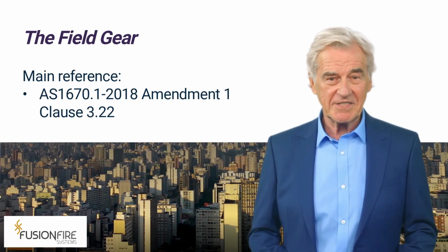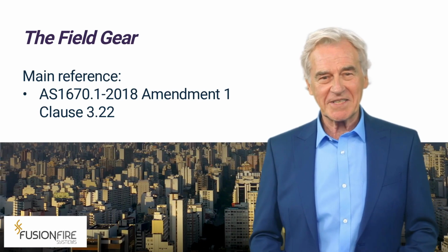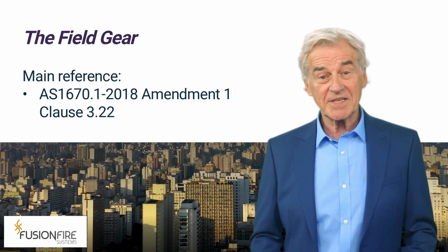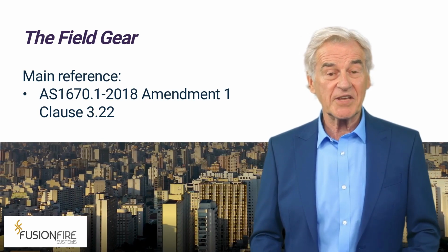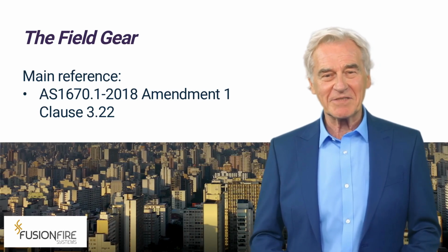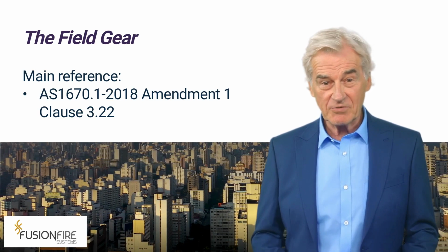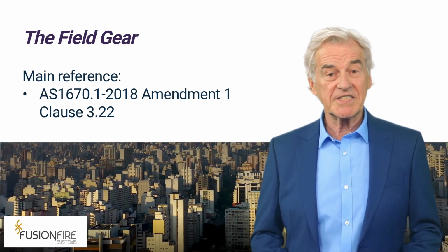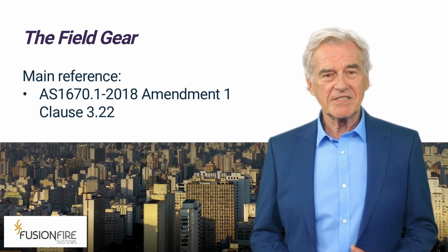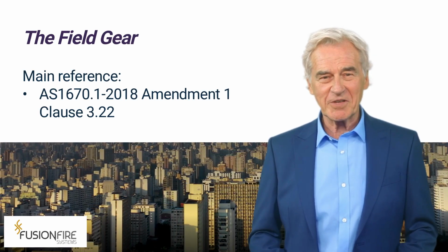However, under 1670 Part 1, you don't need to necessarily use an amplifier and loudspeakers. This is because live speech is not mandatory. In fact, you can use sounders, which generally only produce a tone. In this case, you will need to ensure that sounders are certified to 7240.3. If the sounders are loop-driven and share the cabling with detectors, you must ensure that the installer has used a short-circuit isolator every 40 devices.